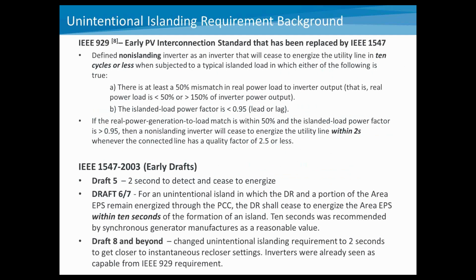I wanted to throw up a little bit of background material on where this requirement came from. Prior to 1547, there was an earlier interconnection standard focused on PV systems called IEEE 929. This has since been withdrawn and replaced by 1547, but if you go back and look at some of the requirements in that document, you can see, for example, that they gave a couple of conditions that the inverter must recognize and then disconnect.